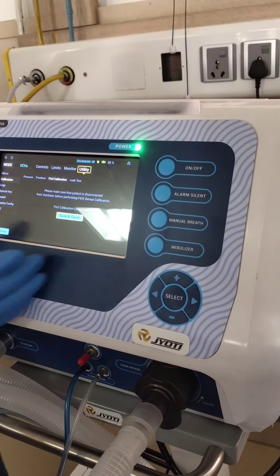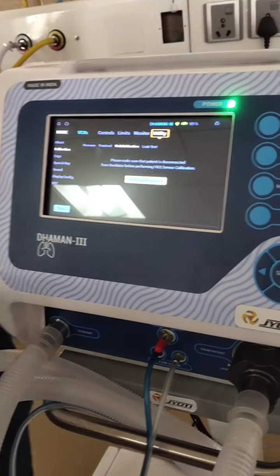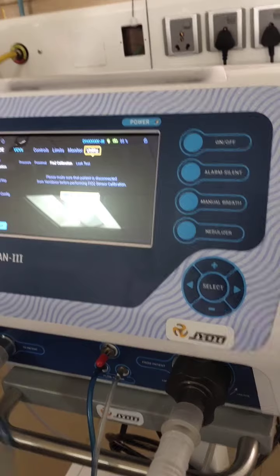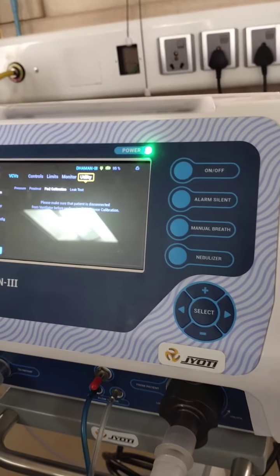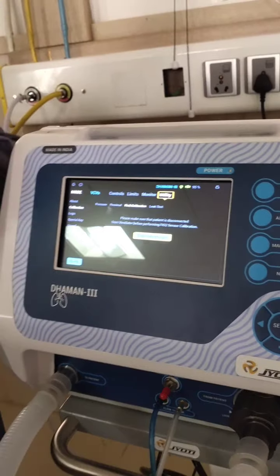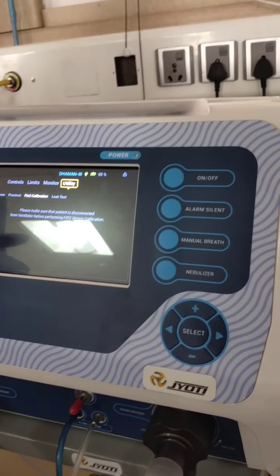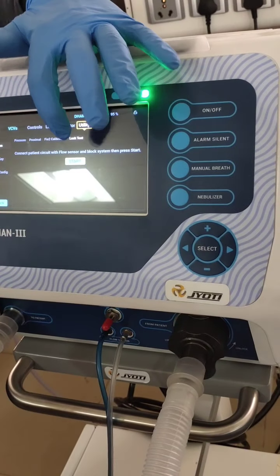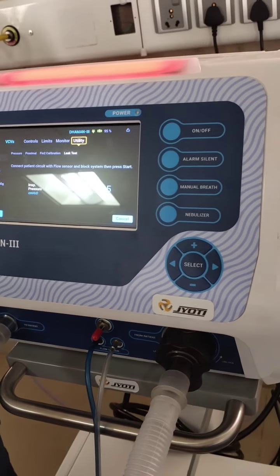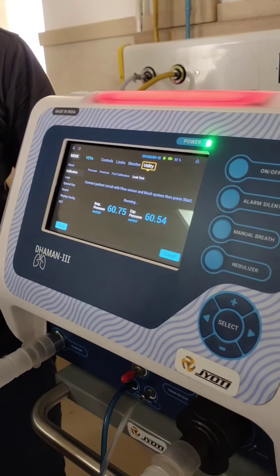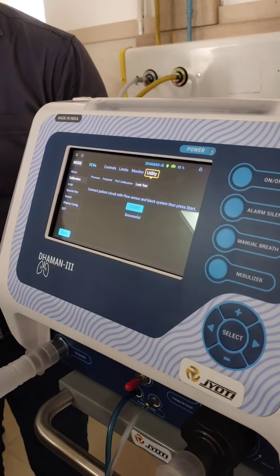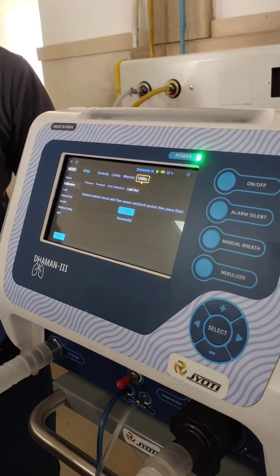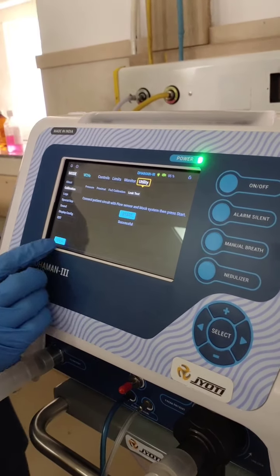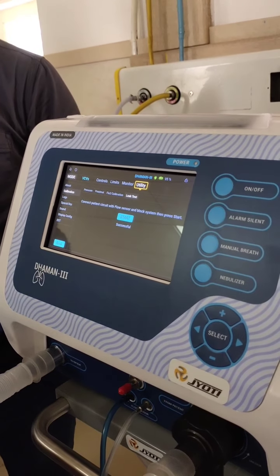Once the calibration is done, like this, save and close. Then check for any leakages in the breathing circuit. We put it in reverse direction, so now we have to open and set it to forward position. Then close this part and start the leak test. The pressure will come to 60, 61, 63, up to 63, and sometimes 59. If it comes like that, it will pass. So these 4 steps you have to check before connecting the patient for ventilation.